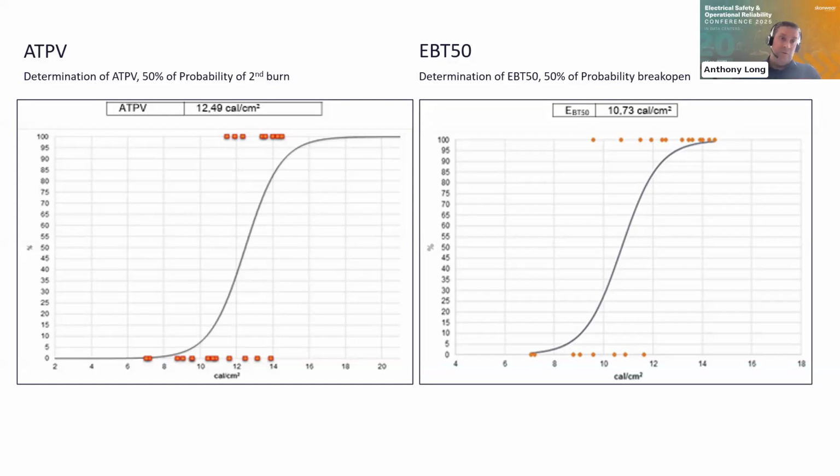So this fabric is rated at 11 cal. You round up when it's over 10.5. So it's 10.73, it's the lower of the two. So this fabric automatically is an 11 cal fabric. This fabric started off as a 12 cal fabric. We marketed this product as a 12 cal fabric, and then it was retested as part of the testing criteria.